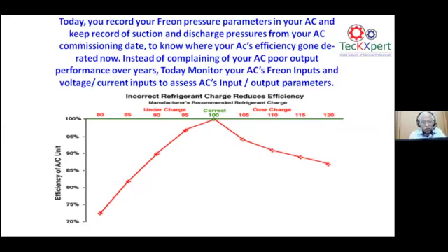The more it is charged, when it is overcharged also, the efficiency drops to 80 to 85%. If it is undercharged, if it has leaked out, the drop in efficiency is almost 30%, down to 70%. So Freon pressure monitoring is very critical, especially on all air conditioners.